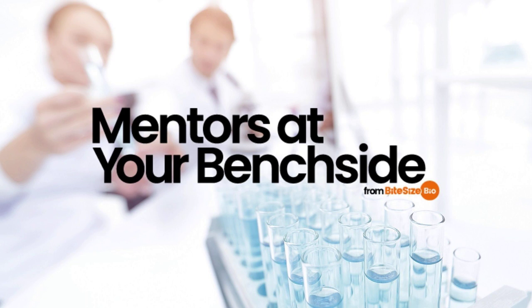The calibration solutions are usually pH 4, 7, and 10. You can even buy little calibration tablets that dissolve in a known volume of water to make the calibration solutions. Calibrate the pH meter with at least 2 different solutions encompassing the final desired pH of your solutions. Better yet, calibrate it with all 3.